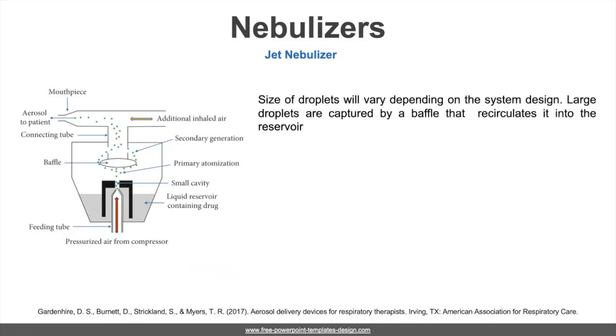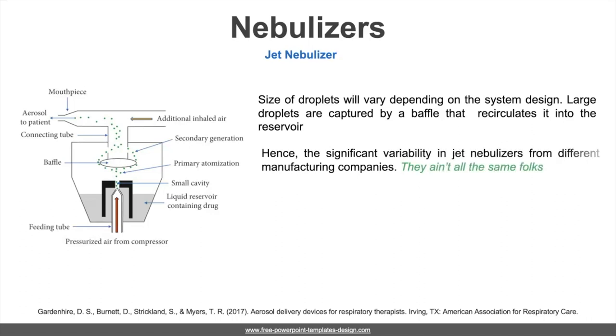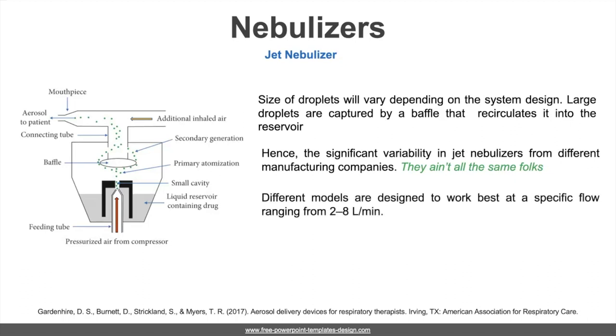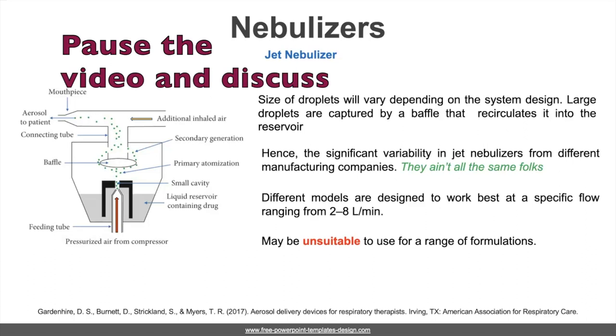The size of aerosolized droplets can differ depending on system design, leading to notable variability among jet nebulizers from different manufacturers. Various models are optimized to perform efficiently within specific flow rates, typically ranging from 2 to 8 liters per minute. It is important to note that jet nebulizers may be unsuitable for certain formulations due to their mode of operation.